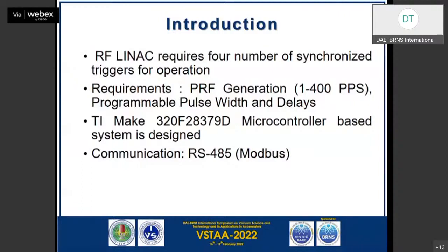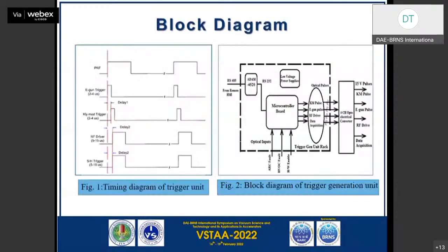So this system has been designed to generate these 4 synchronized pulses, with PRF generation from 1 to 400 PPS, which can be set from a remote HMI, and these pulses will have programmable pulse width and delays. They can be adjusted online. For generating this, we have used a TI make 320F28379 dual CPU processor.